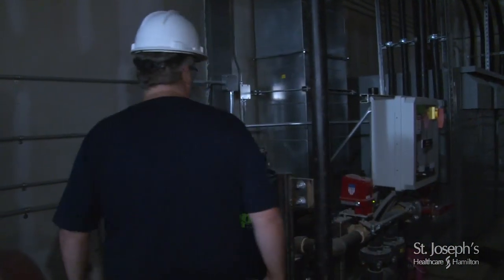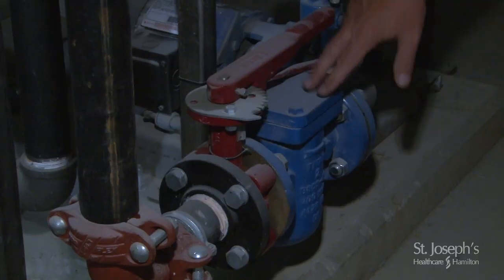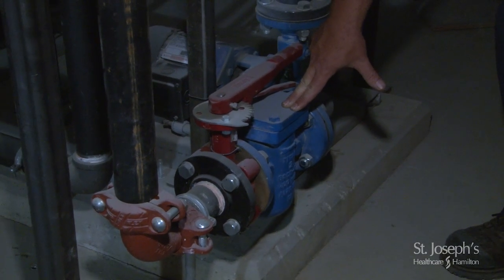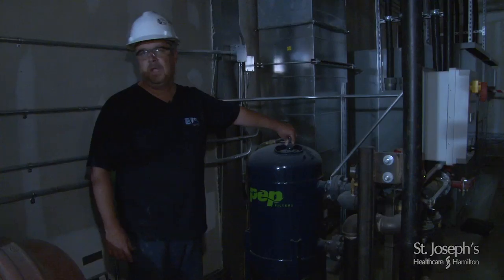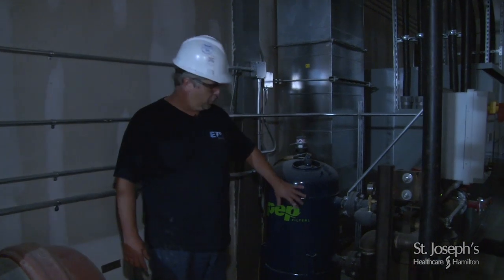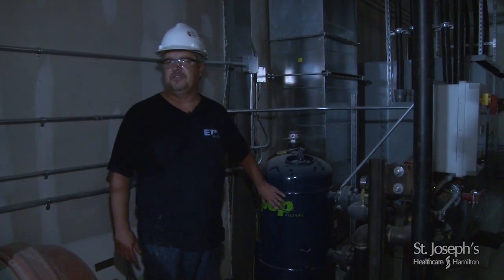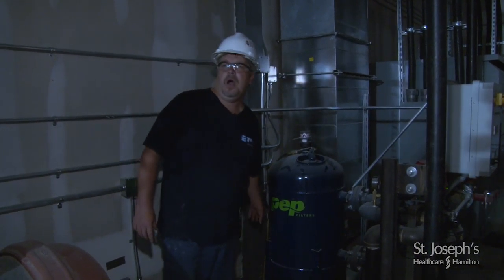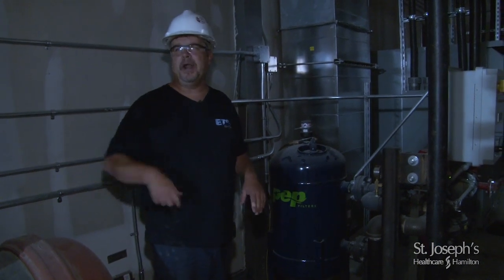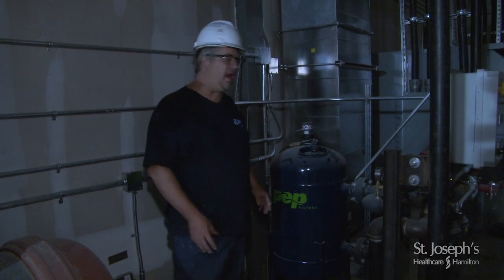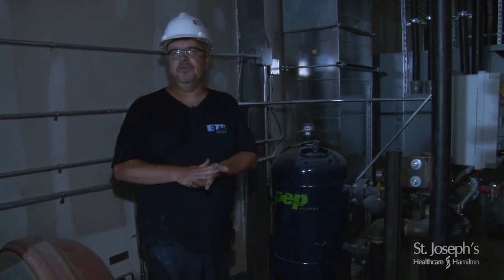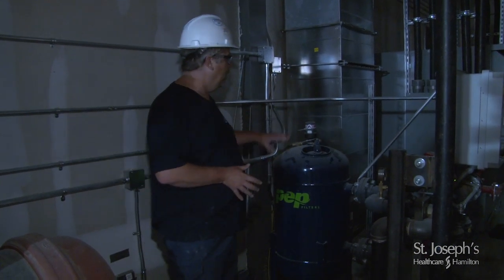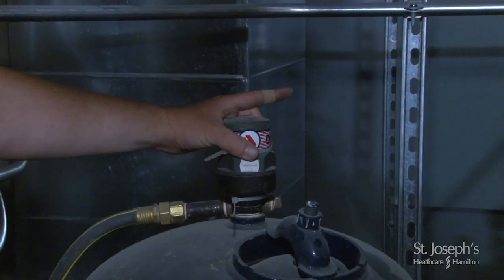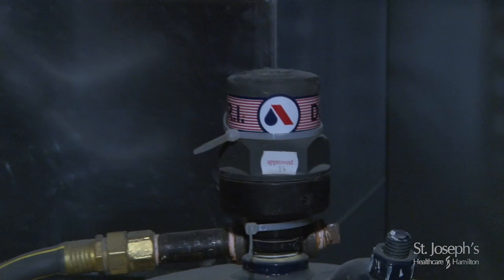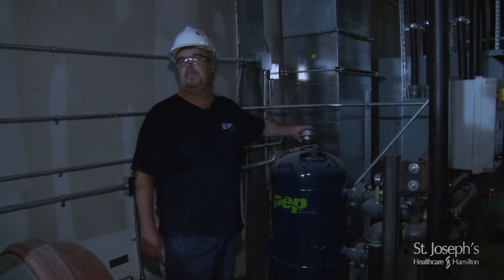If you ever have to replace the filter media, you would have to isolate the tower using the same valves I showed you down here to stop the flow of water. Then you would come over and open up the side port and the top port. That'll relieve any pressure that builds up in here. You would physically drain out all the water that's in this tower, and you would scoop out the old filter media. Once you have the old one out, rinse it with a hose, allow that to drain out, install your new filter media as laid out on the bag and in the operator's manual, and allow the unit to refill itself. It has an automatic purge valve on top, so as you're filling, any air that's trapped in here will be purged out of the top of the filter.